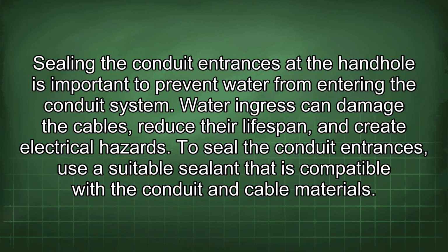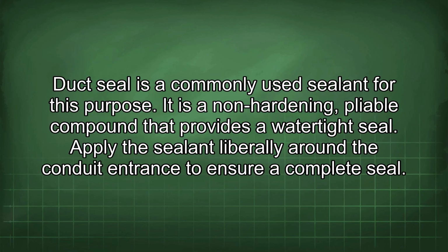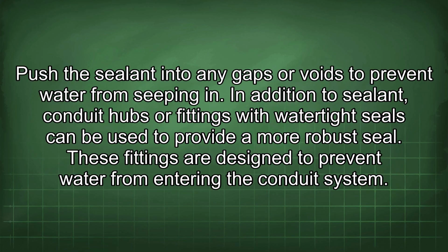Sealing the conduit entrances at the handhole is important to prevent water from entering the conduit system. Water ingress can damage the cables, reduce their lifespan, and create electrical hazards. To seal the conduit entrances, use a suitable sealant that is compatible with conduit and cable materials. Duct seal is a commonly used sealant for this purpose. It is a non-hardening, pliable compound that provides a watertight seal. Apply the sealant liberally around the conduit entrance to ensure a complete seal. Push the sealant into any gaps or voids to prevent water from seeping in.